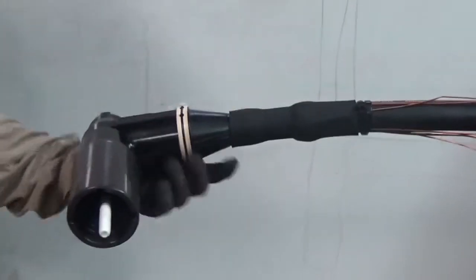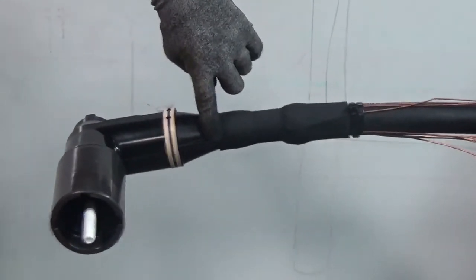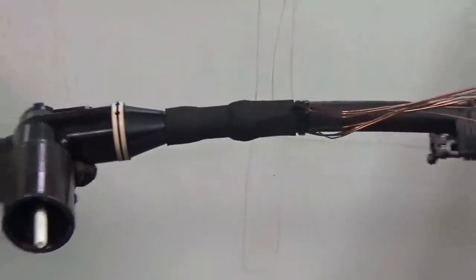You can see where we stopped that on there. I'm going to pull in real close so you can see where you need to stop that cold shrink — right below the Y there. That's where you're going to put a piece of number 12 or number 14 wire and wrap it down to get onto the drain wires.